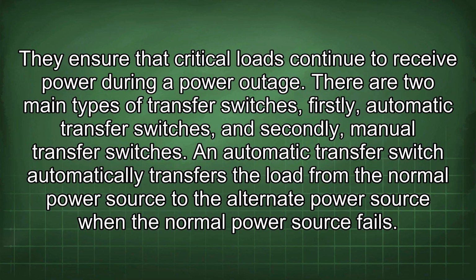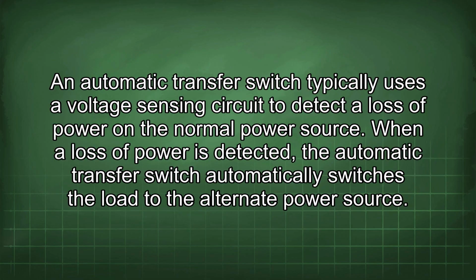An automatic transfer switch automatically transfers the load from the normal power source to the alternate power source when the normal power source fails. An automatic transfer switch typically uses a voltage sensing circuit to detect a loss of power on the normal power source. When a loss of power is detected, the automatic transfer switch automatically switches the load to the alternate power source.